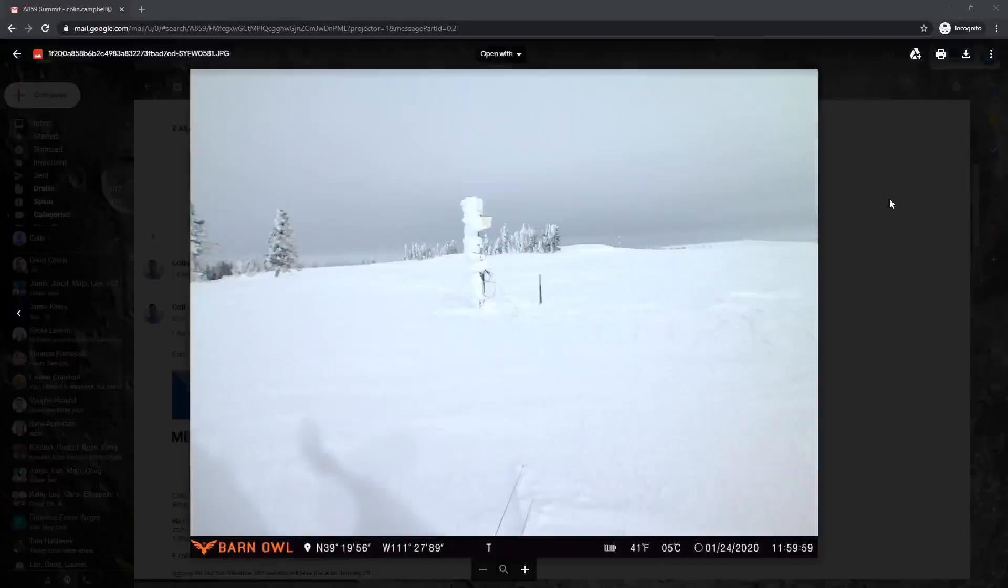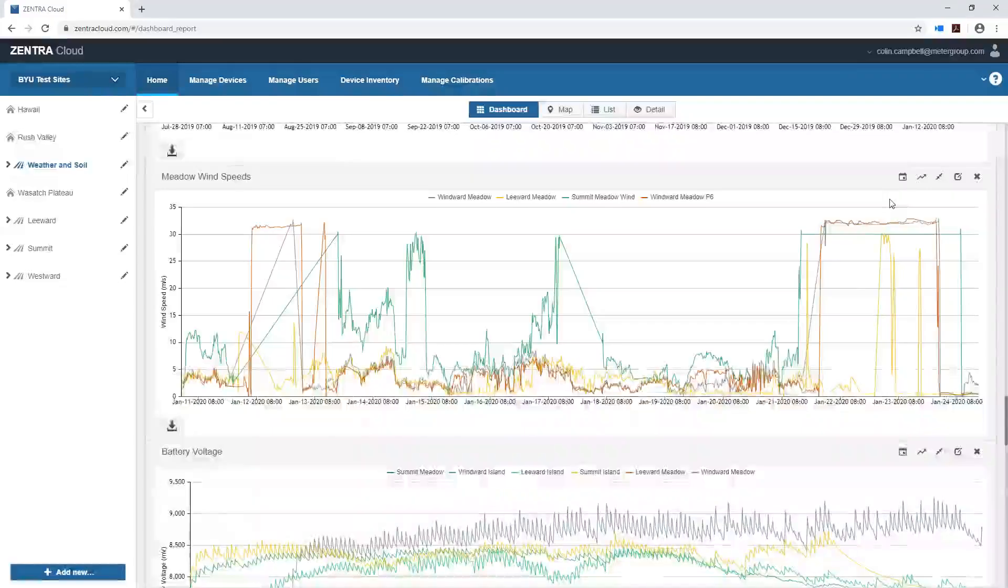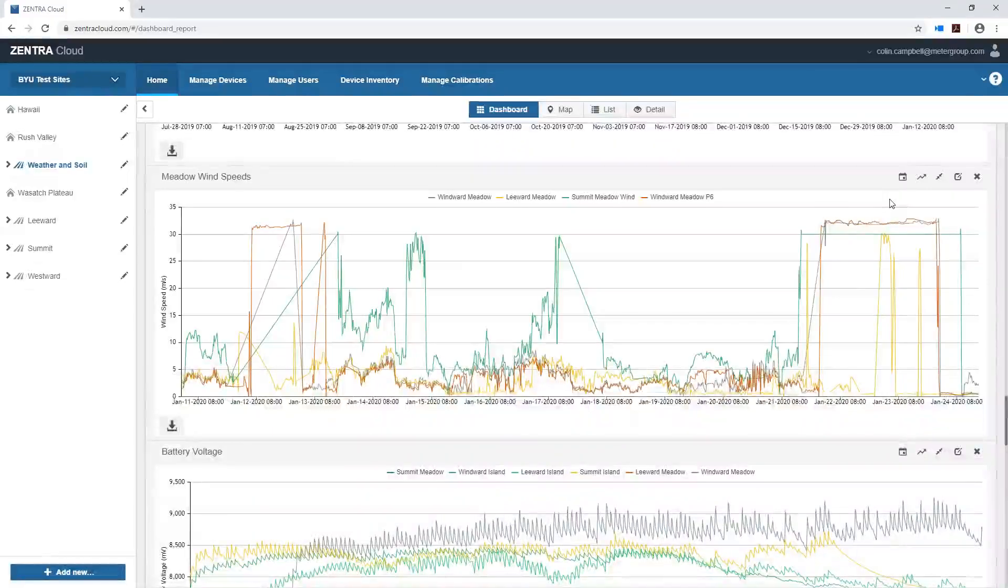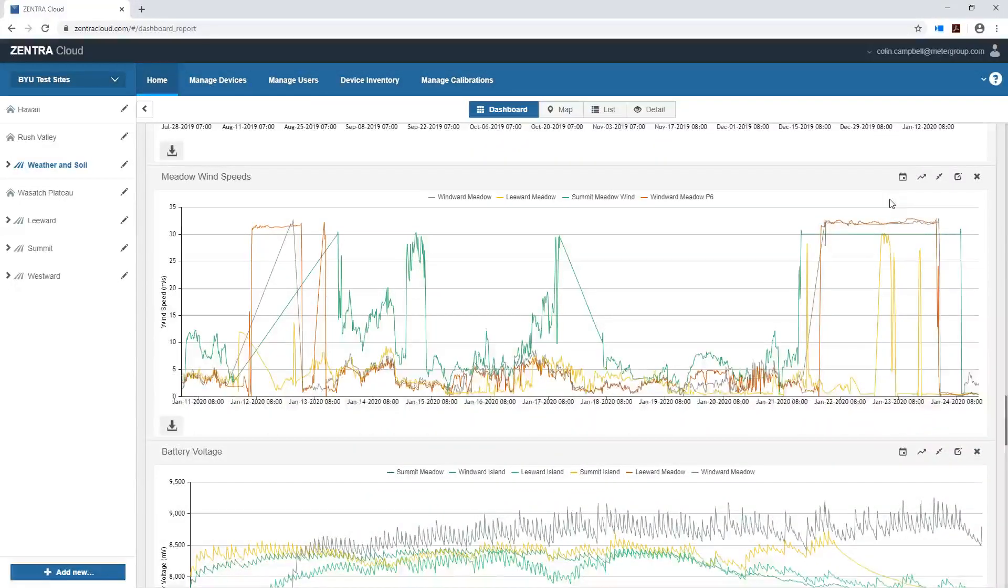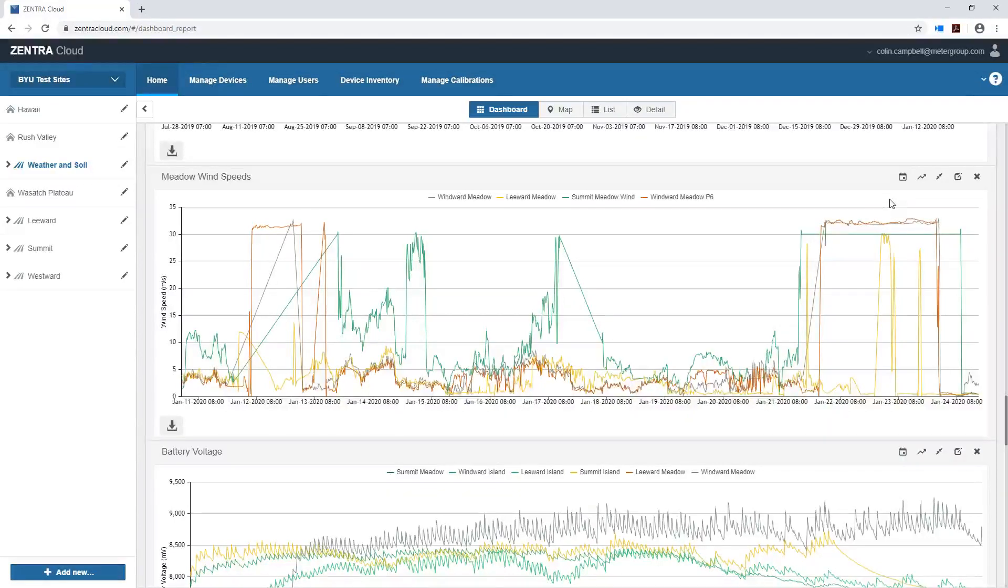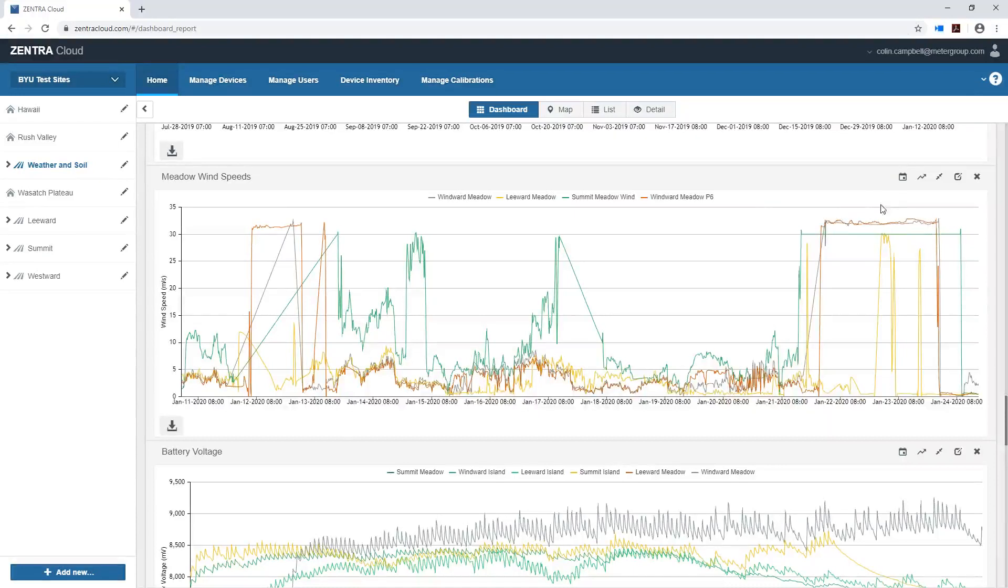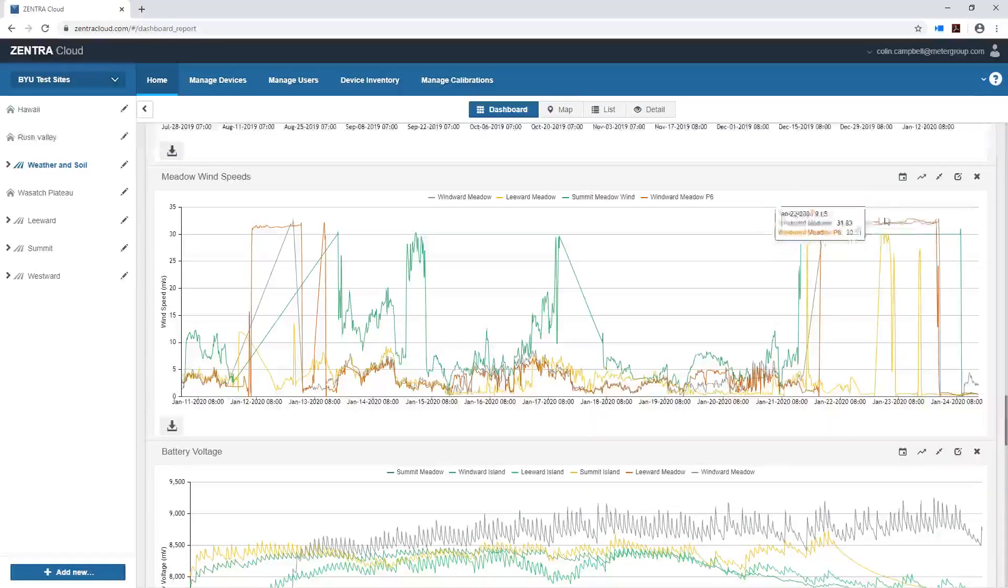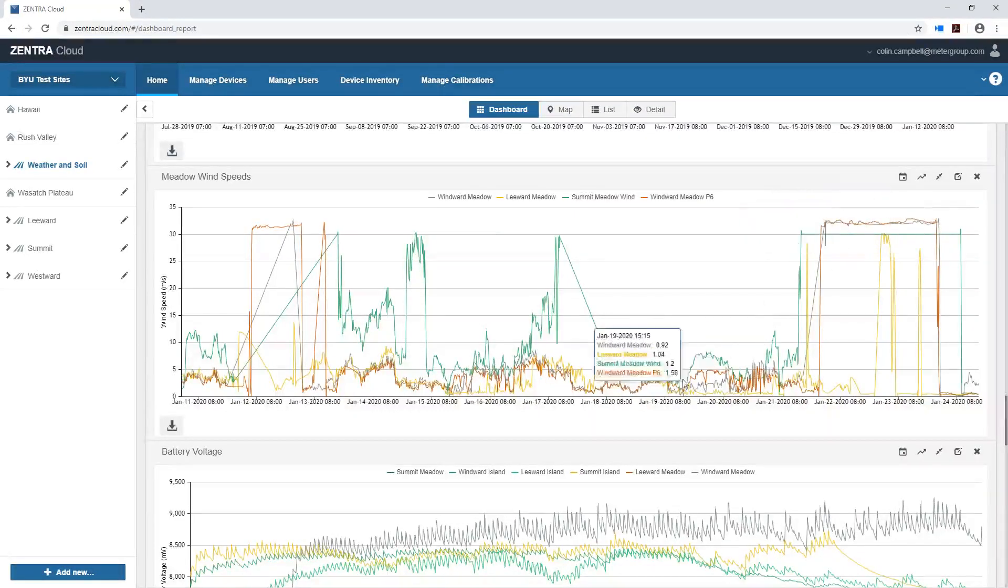But the instrument that's actually making those measurements is the Atmos 41. It's only a three season weather station. And because of that you just can't use it in snow. And so it's essentially producing an error here at 30 meters per second.